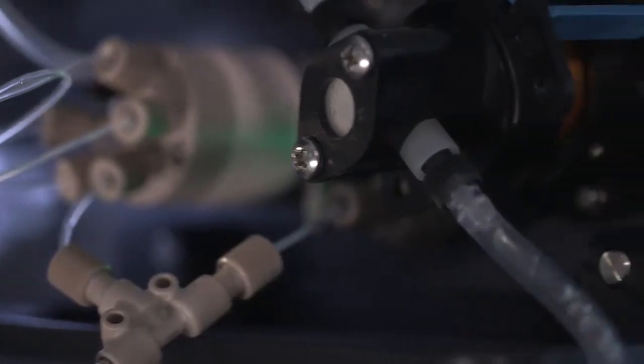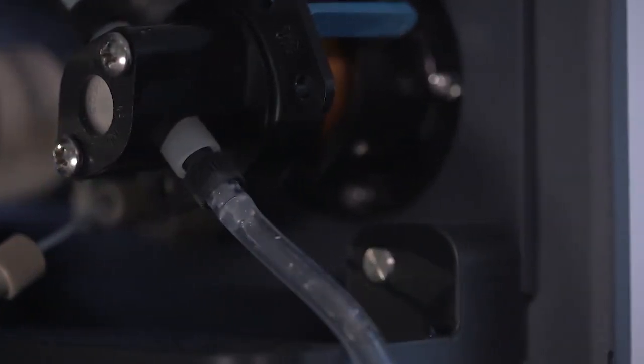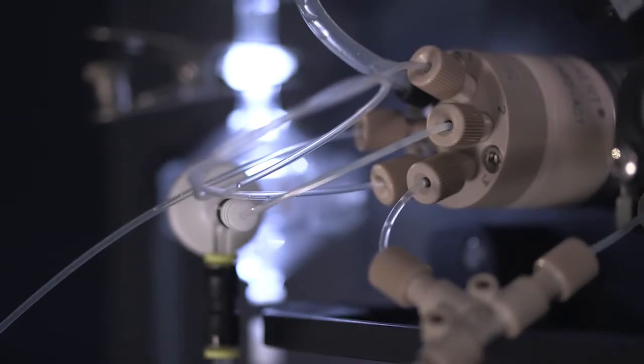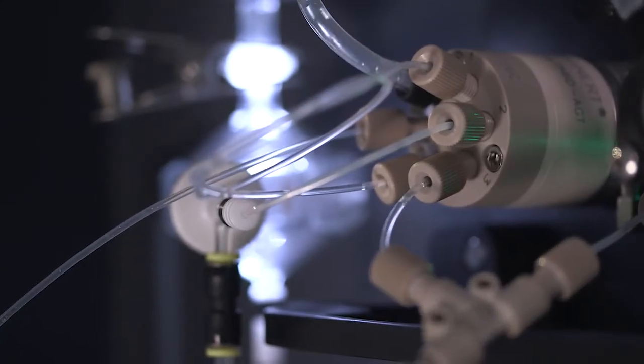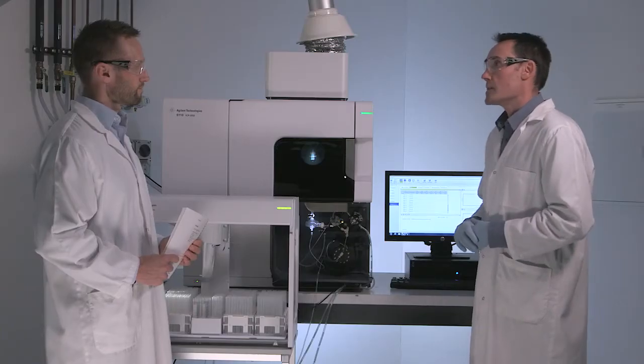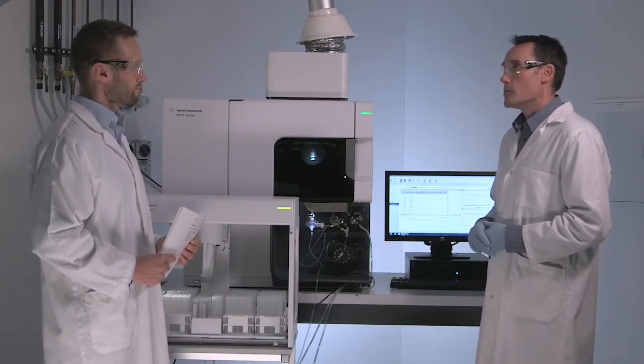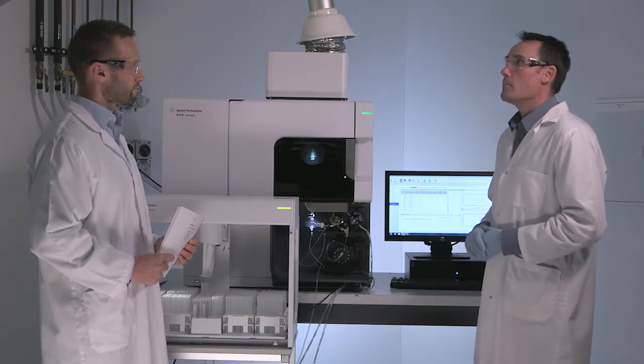Valve methods are able to increase the throughput of sample analysis by being able to perform functions simultaneously. For example, when we use the high-speed positive displacement pump to fill the sample loop, at the same time we are rinsing the spray chamber and the nebulizer. Once the valve switches and the sample injects through to the plasma, we're able to rinse the autosampler probe and half the valve. In this way, we are performing multiple functions at the same time, and we can dramatically reduce the uptake delay, and we can eliminate the method rinse.